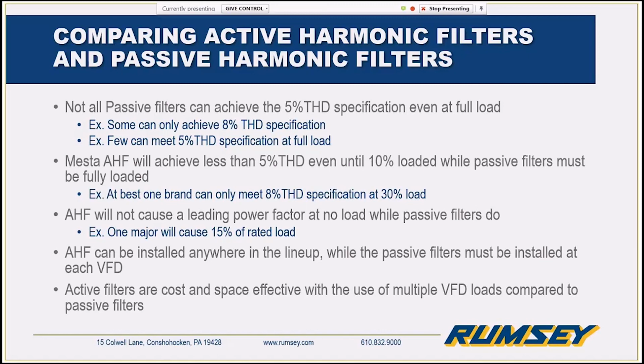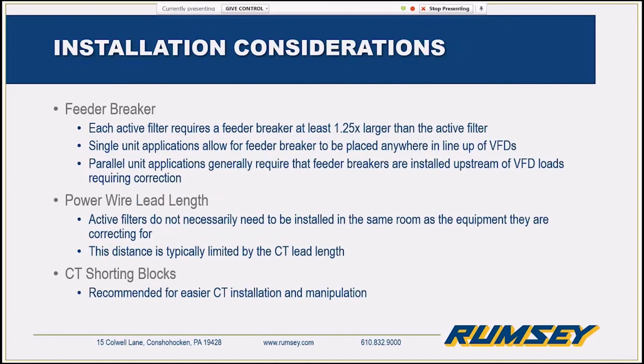And just again, you normally see that these are less expensive options than an active filter, but if you have a large number of VFDs, you start to get into a lot of space constraints when you're working with a lot of passive filters. Again, just needing that feeder breaker, so you have one going in and out, nice and easy to connect to, and then the CTs on the line.